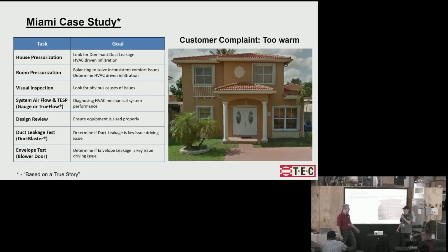That's right, referenced outside. The short answer is 1 pascal. That's just kind of a rule of thumb. But the longer answer is 1 pascal could still be a problem on a really leaky house. It depends a little bit on how leaky the house is. A tighter house, 2 pascals might not be a problem.